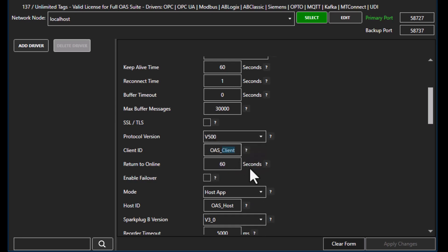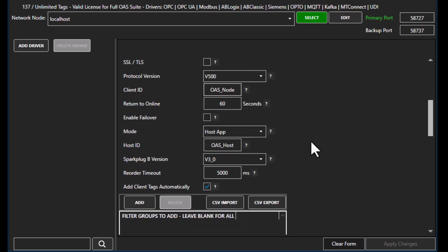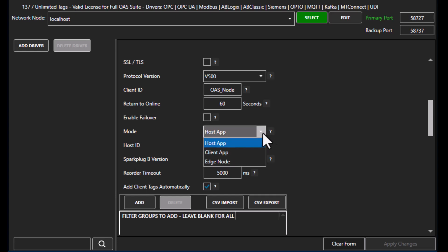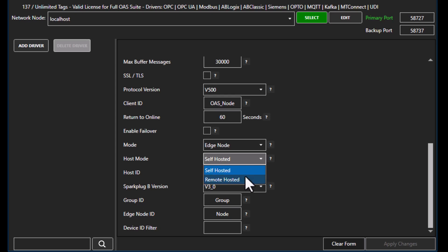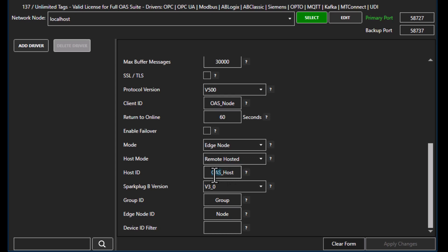The client ID must be unique for every driver interface — in this example I'm going to use 'OAS_Node'. The mode I'm going to set as edge node, so it will be publishing data to an MQTT broker and able to be controlled by a host application. For the host mode, if set to self-hosted it will control itself and turn on when the driver is first activated; if set to remote hosted, the edge of network node will be controlled by another host interface. In this demonstration I'll use remote hosted, and the host ID — which is shared between the host application and the edge node — I'll leave at the default of 'OAS_Host'.